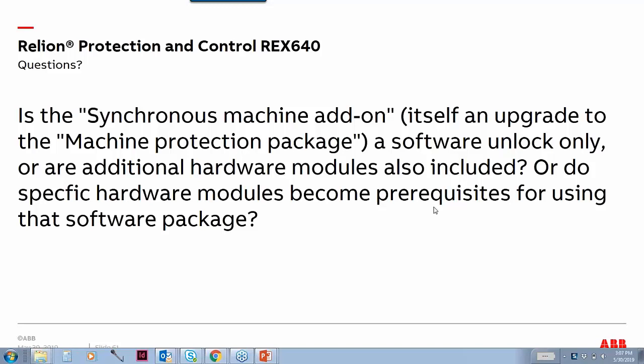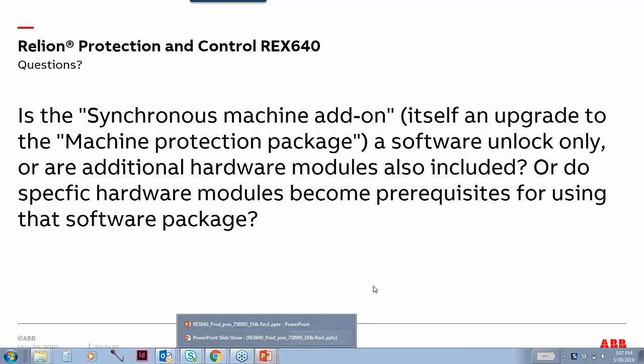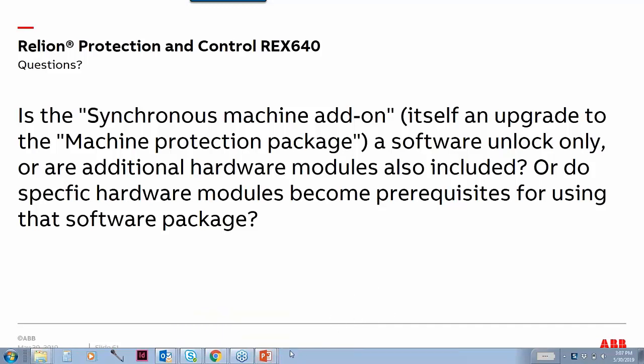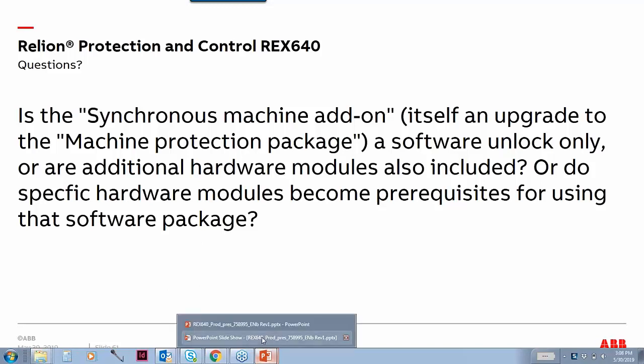Yes, for example, you have the control for up to three breakers, and you can look at it in the way that you can have three relays inside this box. So you can have the elements for different things as long as you have your dedicated analog inputs, for example current and voltage, for each of the machines that you're protecting. You can have the different elements configured for each of the machines. For example, you can have three sync check elements, three overcurrent elements, and three individual voltage elements, one for each of those machines. But it could be up to three.